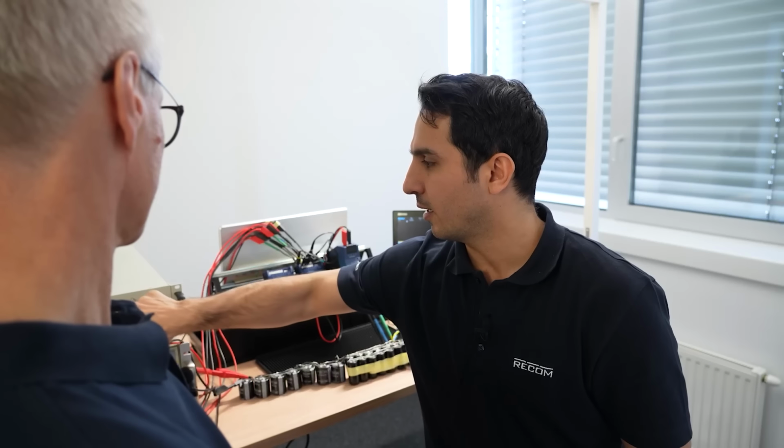Well, in this setup, we have components like our RACPRO AC/DC converter. It is connected to our latest model eFuse. So Moss, let's have the situation why we usually select eFuses. The power supply is running smoothly, but one of the loads, one of the channels, gets into overload or even into a short circuit. In this case, you can see immediately this channel goes into protection mode.